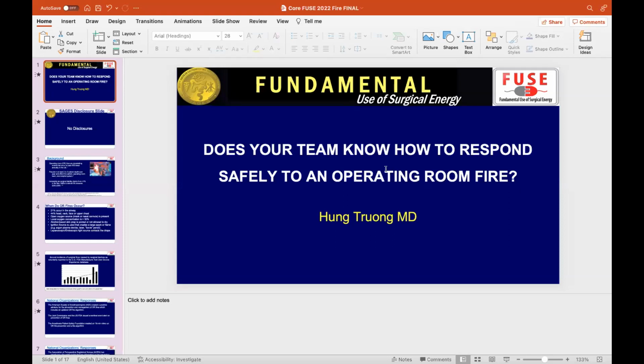The first one is you need to modify whatever surgical energy device you're using to have the lowest voltage possible. So if you use an ultrasonic device, which vibrates, you don't have any electricity in the patient - that's the best. Advanced bipolar has like 120 volts, that's almost nothing, and the current just passes between the jaws of the instrument.